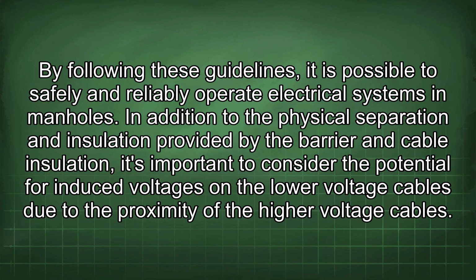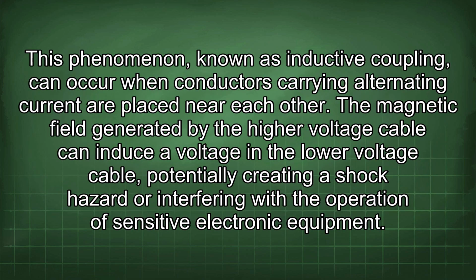In addition to the physical separation and insulation provided by the barrier and cable insulation, it's important to consider the potential for induced voltages on the low voltage cables due to the proximity of the higher voltage cables. This phenomenon, known as inductive coupling, can occur when conductors carrying alternating current are placed near each other. The magnetic field generated by the higher voltage cable can induce a voltage in the lower voltage cable, potentially creating a shock hazard or interfering with the operation of sensitive electronic equipment.